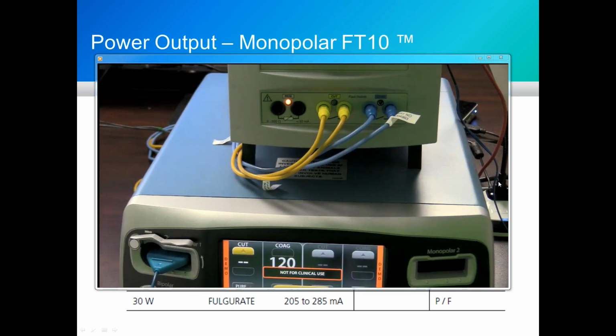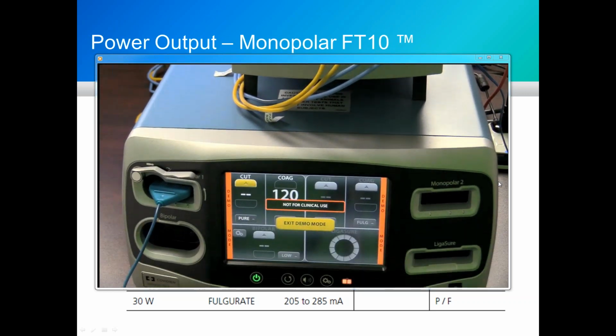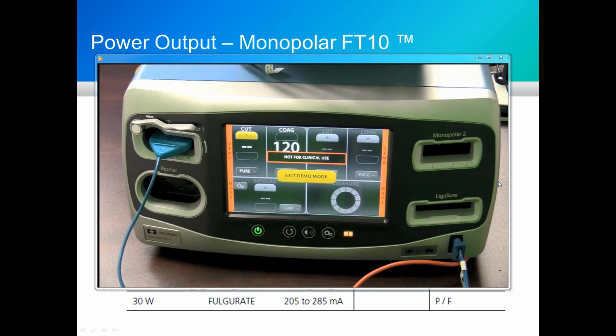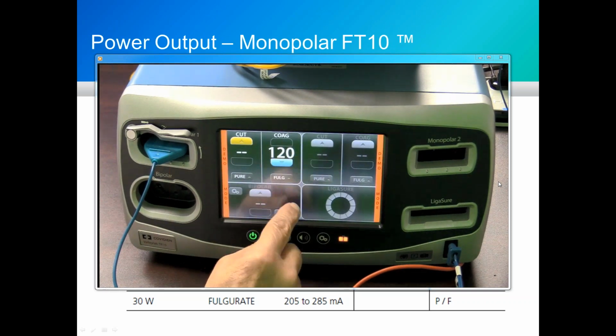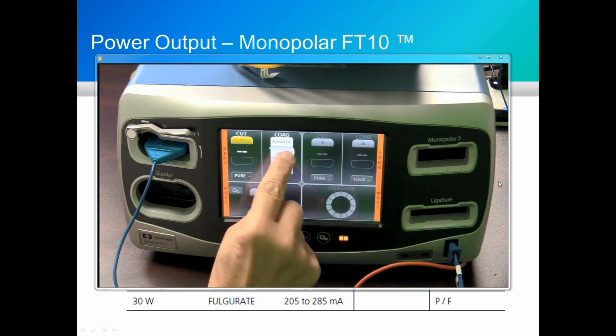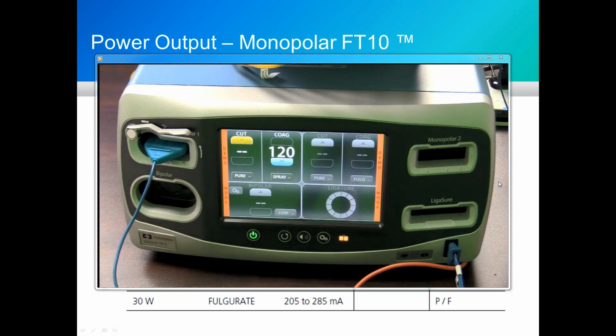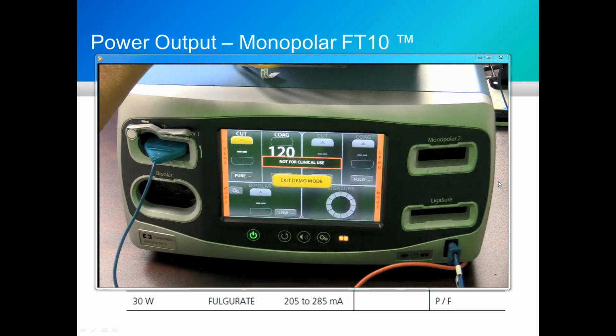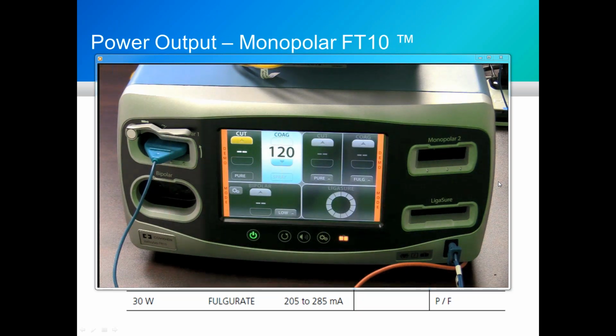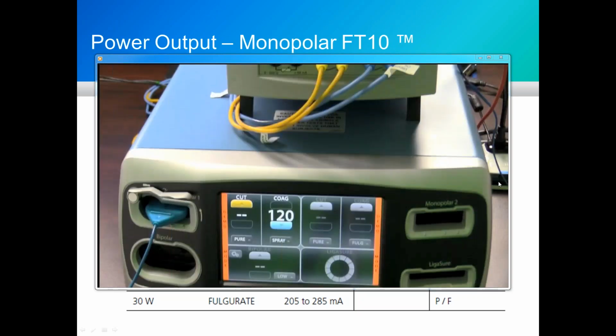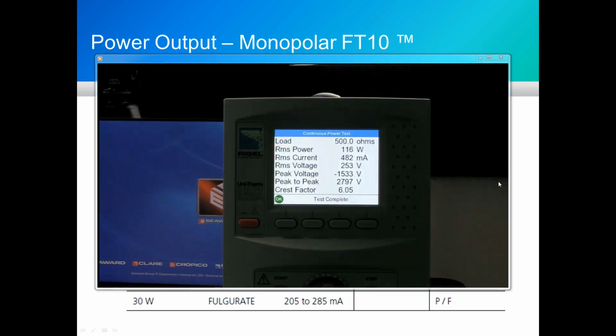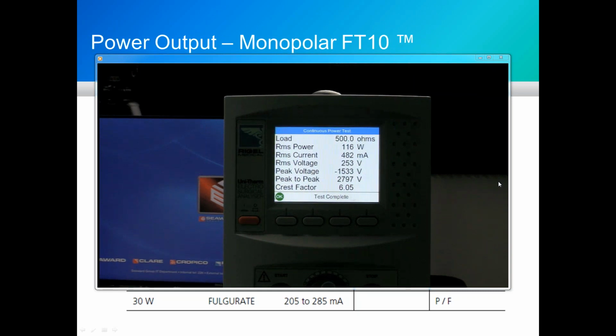Now I have cables going from the front of the Uni-Therm there, and they go to foot switch adapters. So we're mimicking the foot pedals. I hit the start button twice. You see that segment energized. Coag comes on blue for 5 seconds, and there is the data that we capture.